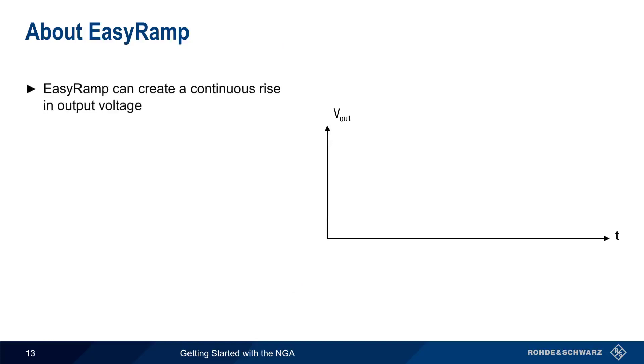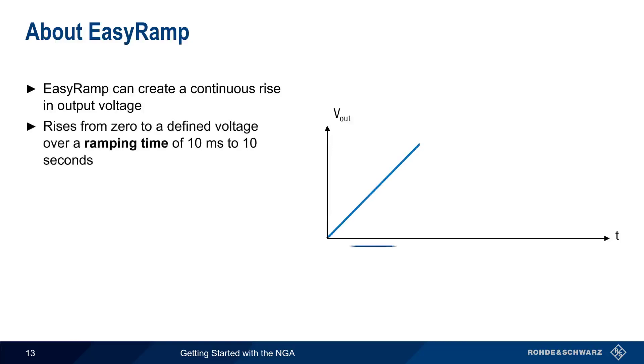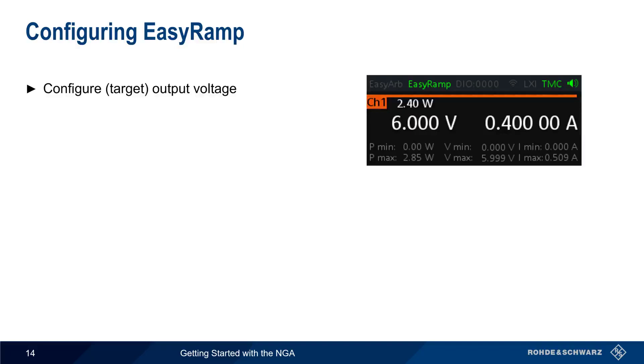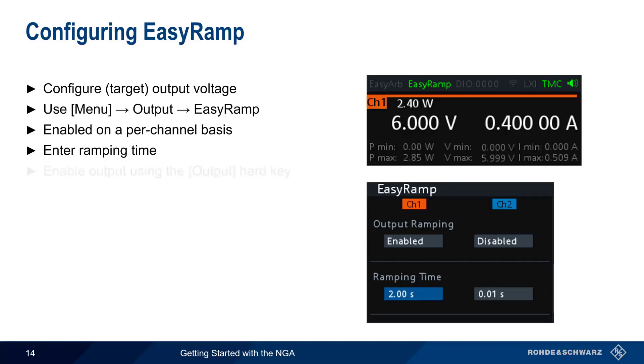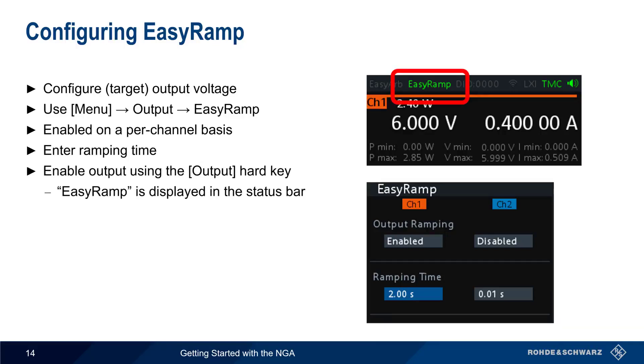As the name implies, EasyRamp is used to create a continuous rise, or ramp, in the output voltage. The output voltage starts at zero and then rises to a defined voltage over a ramping time from 10 milliseconds to 10 seconds, after which it remains constant. To configure EasyRamp on the NGA, first configure the final or target output voltage as usual. Then press the menu hard key and select output EasyRamp. EasyRamp is enabled on a per channel basis, the only parameter being the ramping time needed to change from zero volts to the final output voltage. Once EasyRamp has been configured, ramped output is enabled using the output hard key. Note that during operation, EasyRamp is displayed in the status bar.